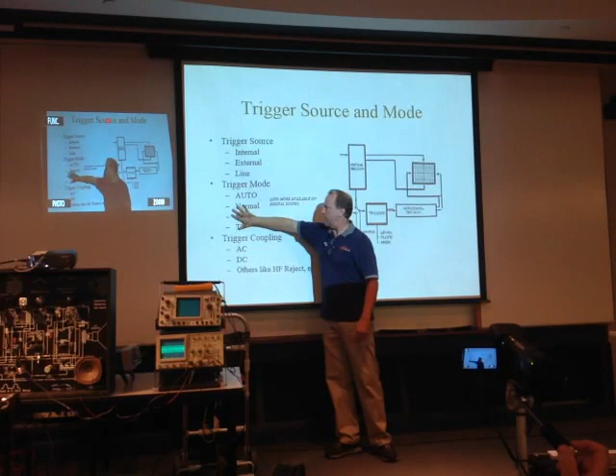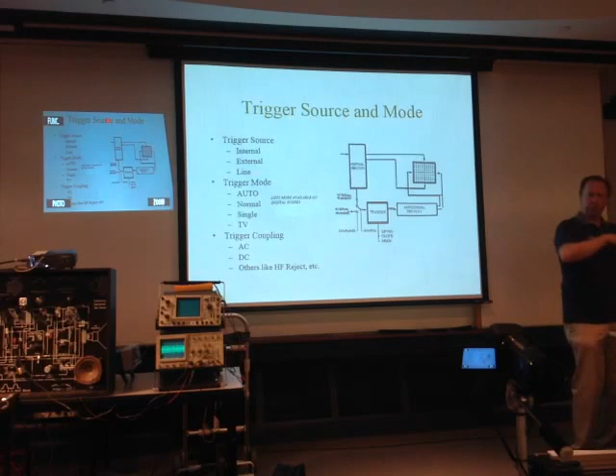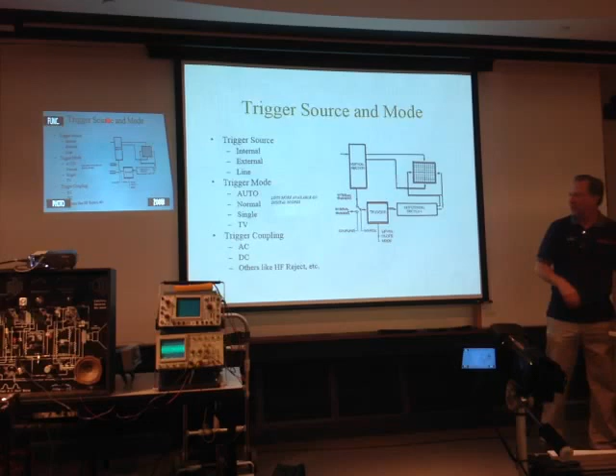Trigger coupling. Just like on the vertical input, we can take the signal that we're sending to the trigger circuit and AC couple it or DC couple it. If we want to remove the DC content, we can AC couple it and just trigger on the ripple portion, the small AC portion riding on top of the DC. Some other scopes will have other coupling modes like HF reject, which is high frequency reject. So you've got a low frequency signal with some high frequency stuff on it, and I want to trigger on the low frequency portion. The HF reject is a low pass filter that will get rid of the high frequencies. But again, most of the time you're using one of these two.